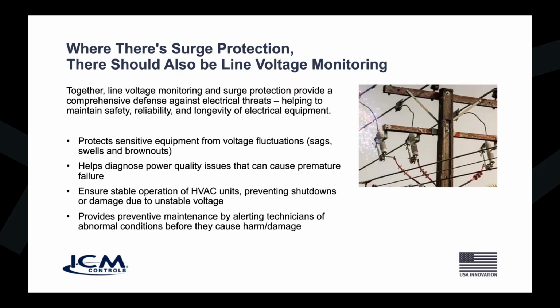Whereas a voltage issue, like a grid level change, maybe that's everybody's turned on their air conditioners and the peak power needs to be increased because it's putting such a demand on the grid that the power company has to raise the grid from 240 to maybe 250. Well, that can be damaging to some equipment. And a surge protection device will not protect against gradual voltage grid level changes like that, so if you haven't got a device that can protect against that, then you're still going to be in trouble.